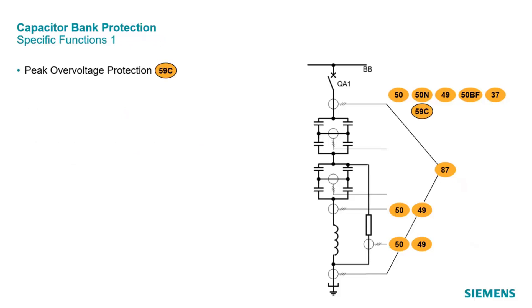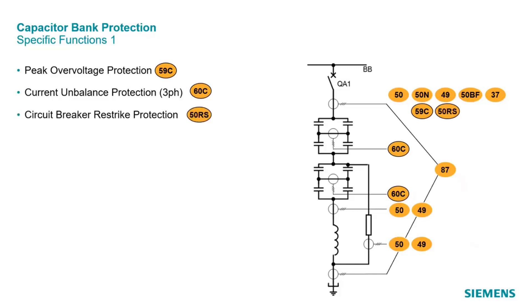As specific functions for the capacitor bank, we have the peak overvoltage protection, which protects the capacitor's dielectric against too high voltages. The current unbalanced protection can be used in a capacitor bank with an H topology, as shown here, to detect the failure of single or several capacitor elements. The circuit breaker restrike protection is responsible for finding restriking currents after the circuit breaker has opened — a phenomenon especially important for circuit breakers of a capacitor bank.